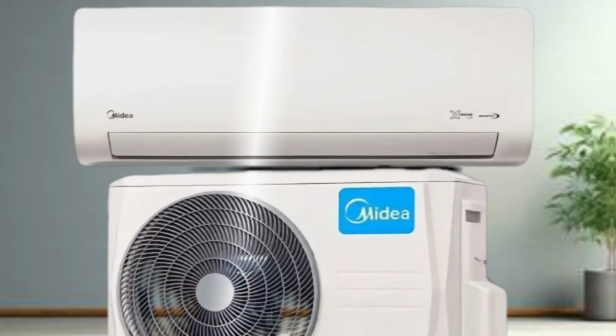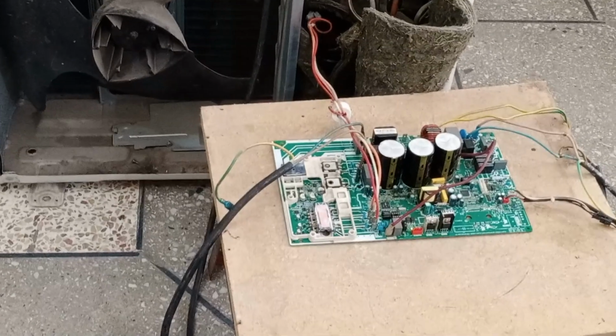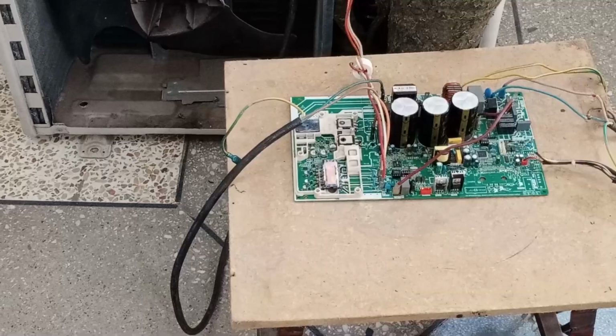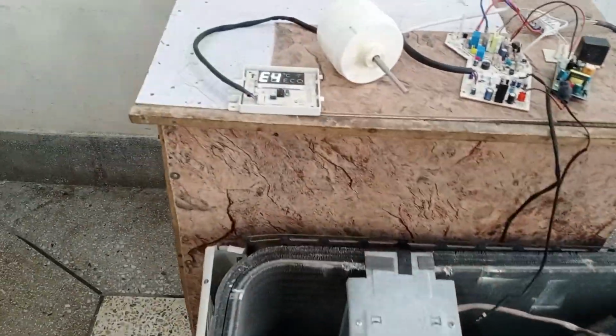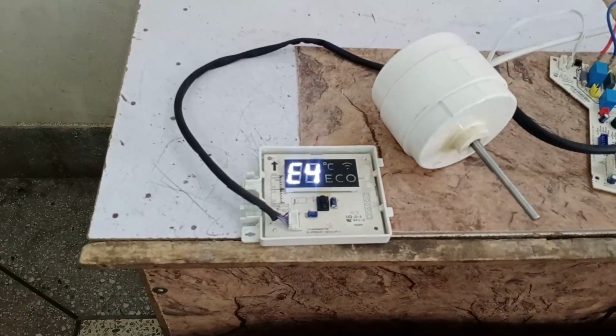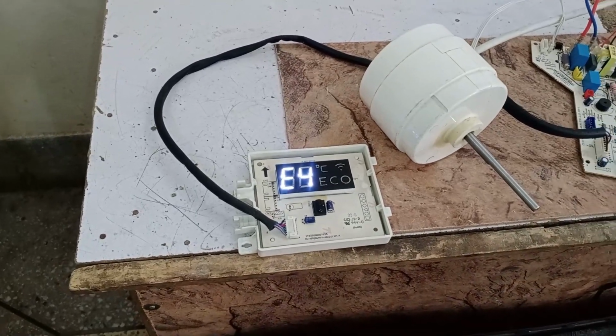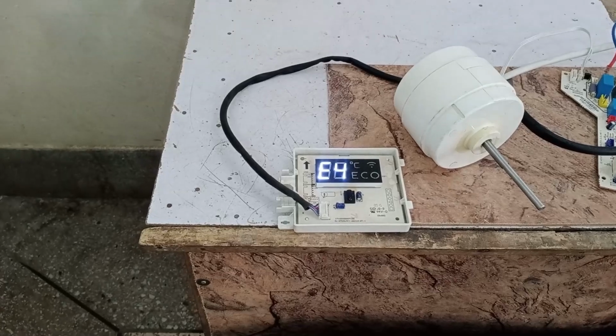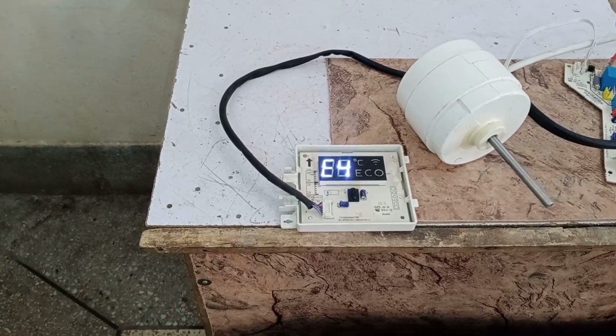If you have a Midea mini split air conditioner, this is its outdoor PCB. We are currently checking the error codes on this PCB. The error code currently displayed is E4. The meaning of E4 can vary between 1 ton and 1.5 ton units. However, in this case, E4 means that the room temperature sensor is faulty or short-circuited.